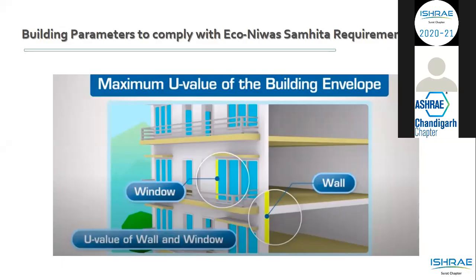D is the thickness of your wall and K is the thermal conductivity of any material which you will be using in your building. K is the thermal conductivity which you will receive from your vendor or manufacturer, and D is the thickness of your wall assembly. So R is equal to D by K and U is equal to 1 upon R. In that manner, you can calculate the U value, and your building envelope will be more energy efficient if the U value of your wall and roof is less than 0.4.